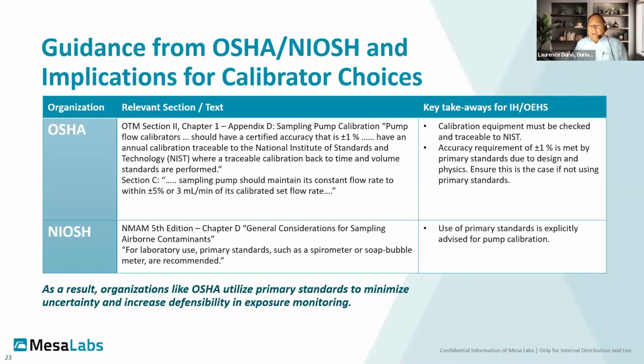OSHA and NIOSH have guidance. Their general guidance for both of them is plus or minus 1%, with a recommendation for the use of primary standards as opposed to secondary standards. Obviously NIOSH is purely advisory, but OSHA, in a lot of its substance-specific standards, goes beyond just a recommendation and mandates the use of a primary standard. And they use primary standards in their own work because it gives them defensibility.